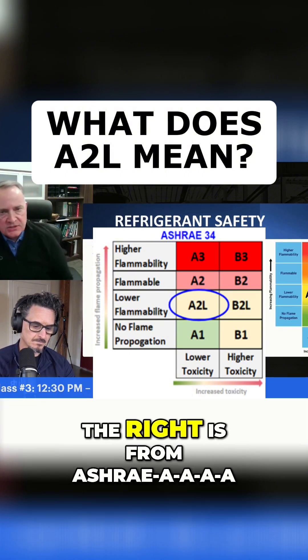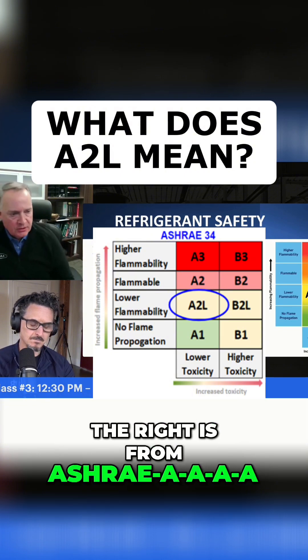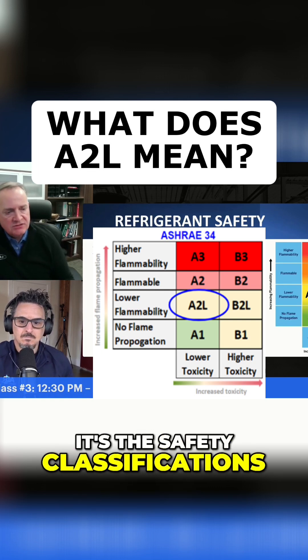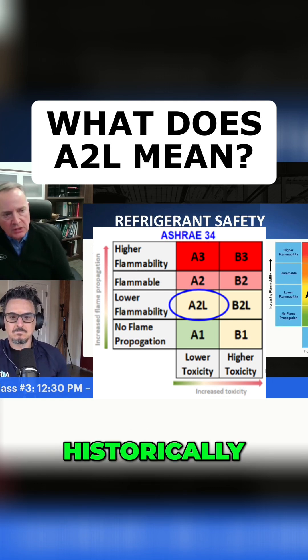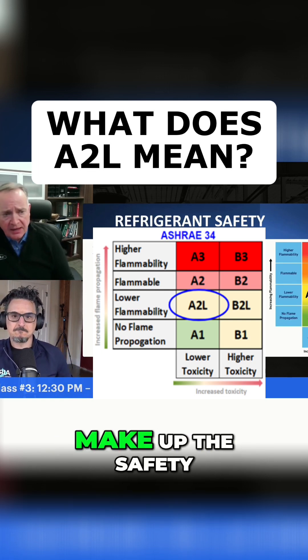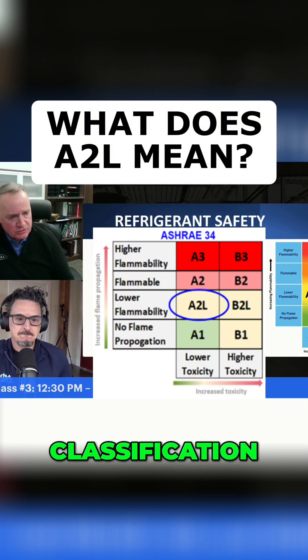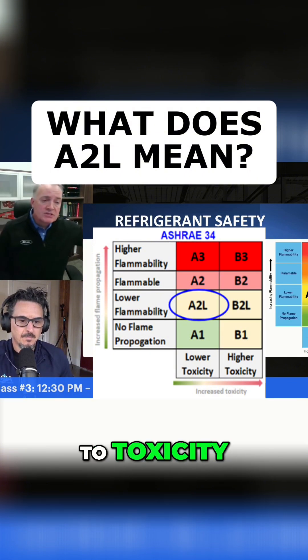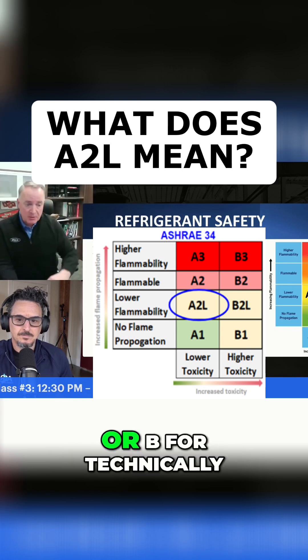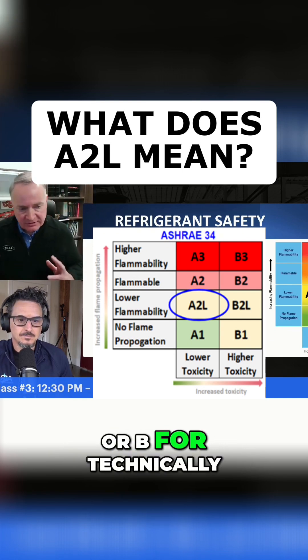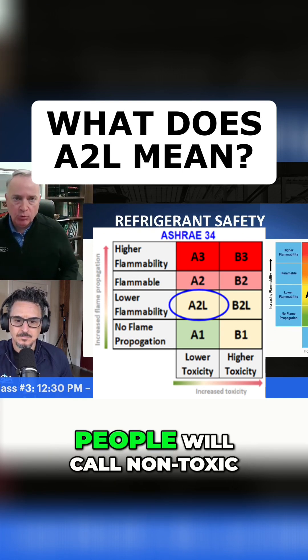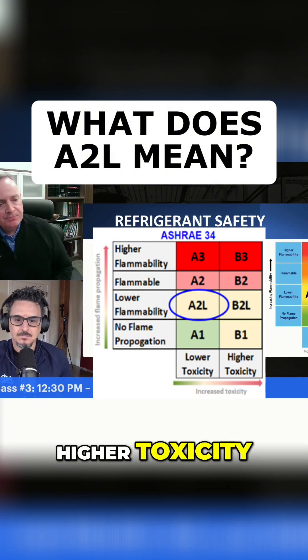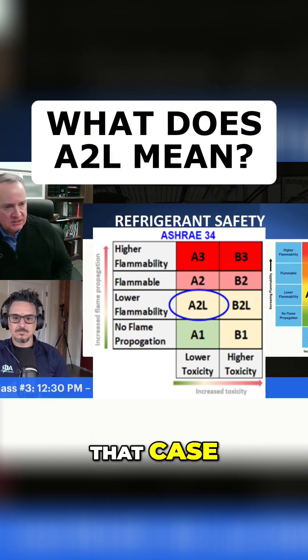This chart here on the right is from ASHRAE 34, which talks about refrigerant safety — the safety classifications for refrigerants. Historically, there are two digits that make up the safety classification. The first digit refers to toxicity: either an A for lower toxicity, which a lot of people call non-toxic, or B for higher toxicity.